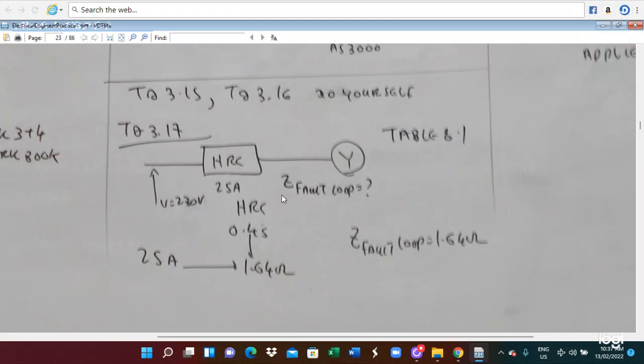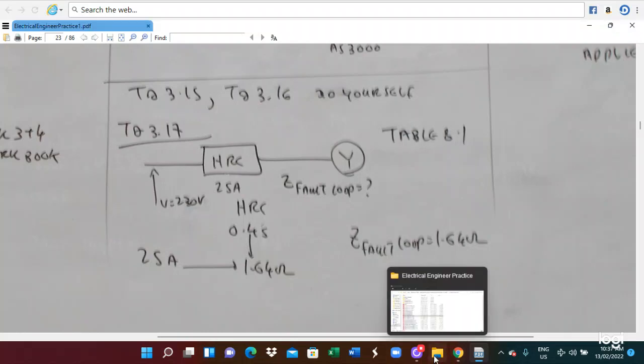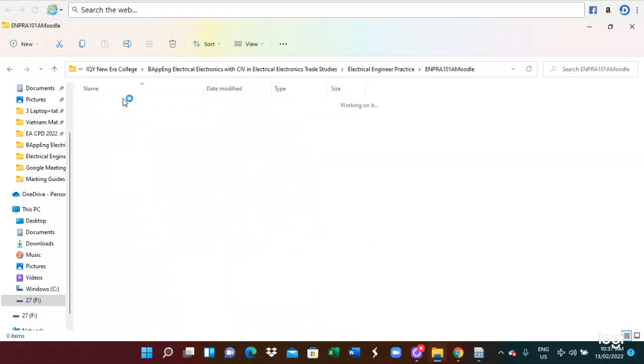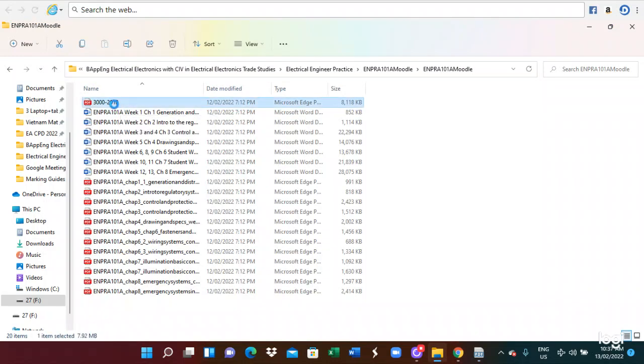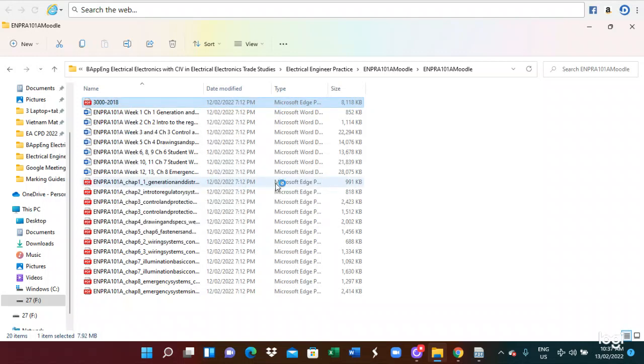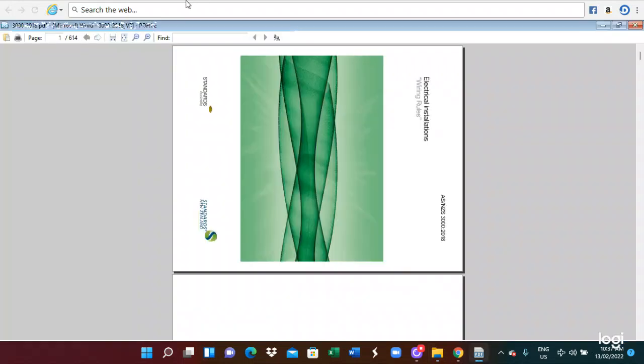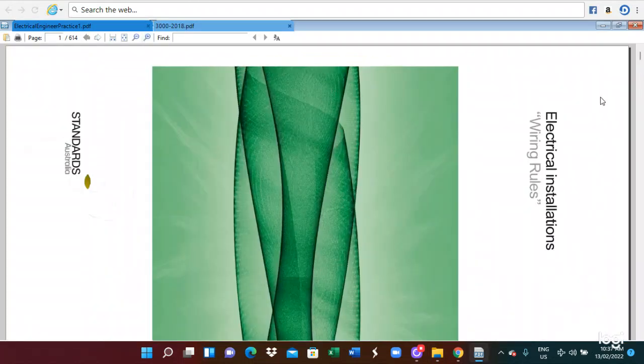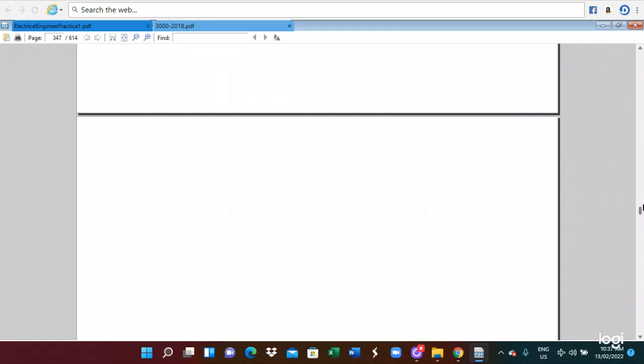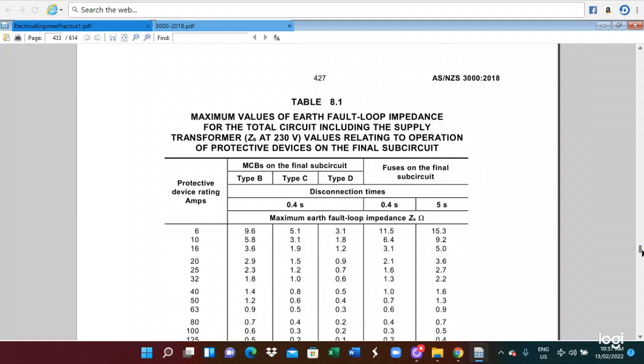So in this case, we have to calculate the fault loop impedance for the installation. We also have to refer to table 8.1 for the fault loop. So we refer to the AS3000 rules and table 8.1 as well. We go to section 8. So this is table 8.1.